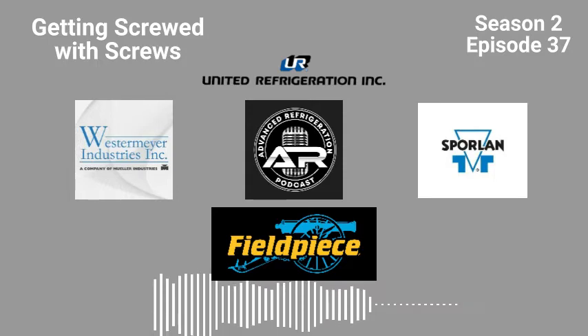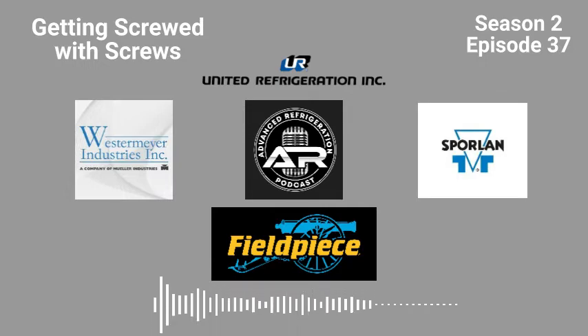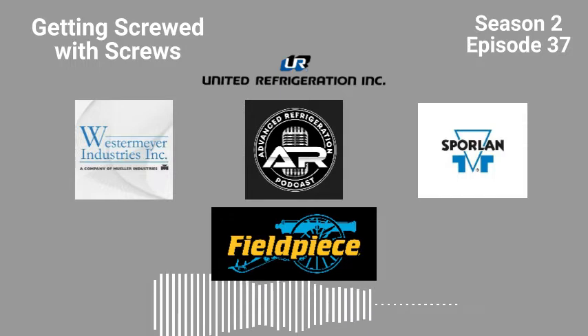Yeah, so usually if you don't have the right oil flow, the bearings will take a crap, the thrust bearings, and then you'll get an electrical short in the back. I'm doing a startup here, and I'm like, we can't get the box down to temp. The rack's overloaded, so I'm going to fire up number 4. I'm going to figure out what's wrong. The service department's got a contactor coming. There's supposed to be a service guy coming. I'm like, well, this doesn't seem right. I turn on number 4 compressor, and I swear to God, I have never heard a compressor make such a horrendous noise.